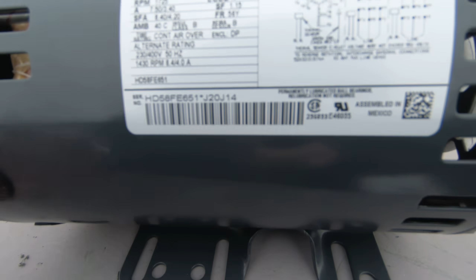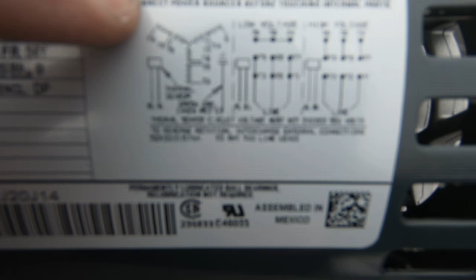Now we're on a low voltage unit, which is 208, 230. So basically T5, T6, and T4 are all gonna get wire nutted together. T9 and T3 will go to one leg. T8 and T2 will go to the second leg. And T7 and T1 will go to the third leg.